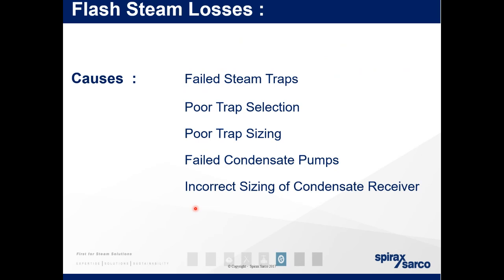Failed condensate pumps. If you're not pumping back condensate and you have no pressure to do so, it's sat there, it's not going back to your boilers, and it's not giving that heat back to your feed water. And incorrect sizing of condensate receivers. If your receiver is too small, you're going to have stall, you're going to have a backup of condensate. It's not going to return as fast as possible, so you're going to see heat losses and various other things. Are there any questions at that point?